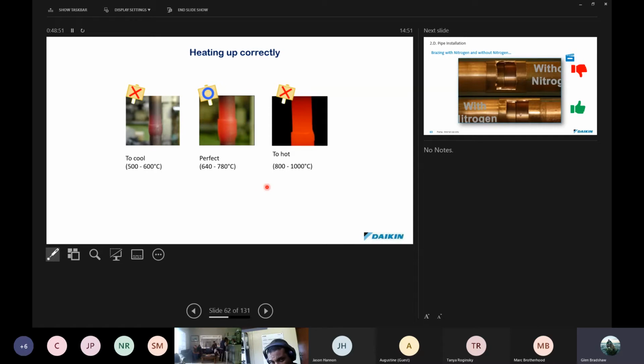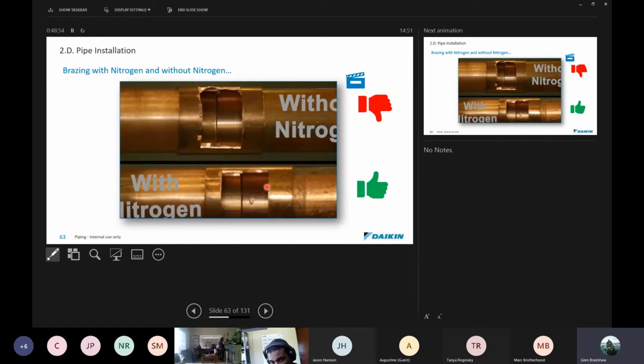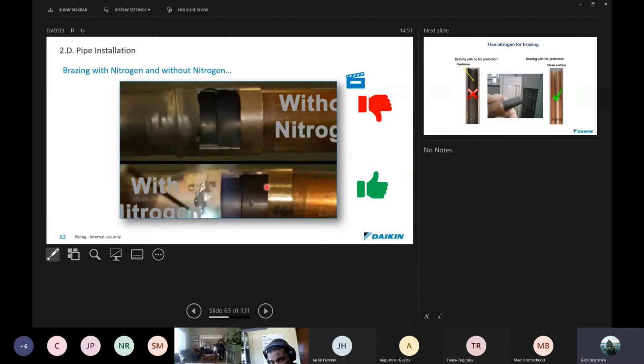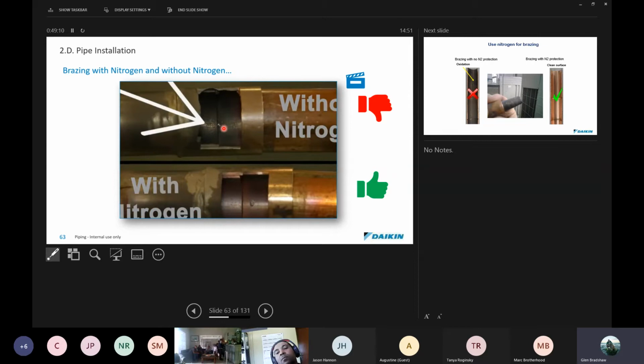So when welding with nitrogen, what does it affect? In this video over here, you'll see that the top pipe is without nitrogen and the bottom pipe is with nitrogen. And then I'm going to weld it. Immediately we can see the difference in the finish of the weld. And you can see there, some of the flux already started to break off as the weld started to cool. So we don't want this inside the system. This is detrimental to any refrigeration system, and it will definitely reduce the life of a unit.